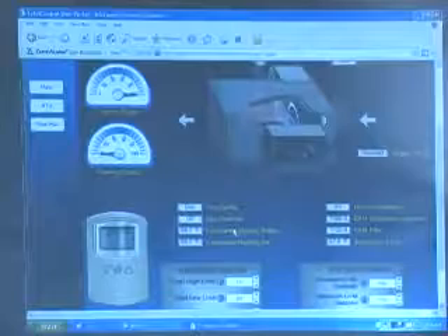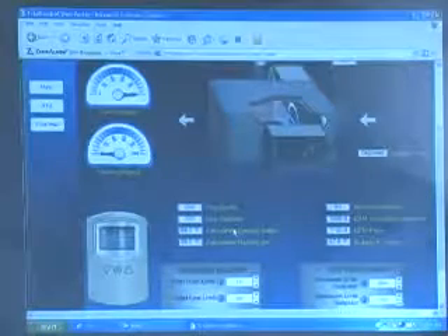We'll refine that further in specific projects. We have projects where the engineer will decide that the building operator, who's maybe at a higher level than most, let's say this could be a manufacturing business, may want access and control over the deadbands and other tuning parameters. You'll notice if I hover over the points, our front end will actually tell you what the point is. So this is a loop. This is a signal from a control loop. That control loop is actually the PID functionality of the cooling set point.